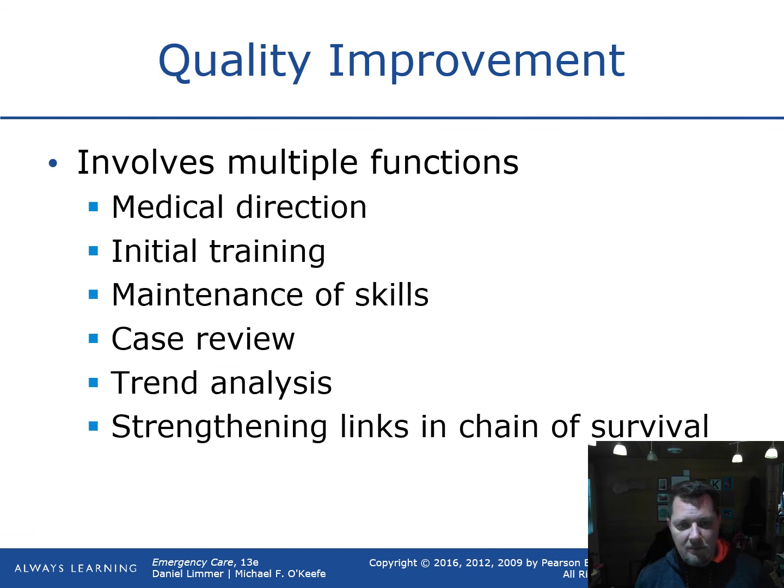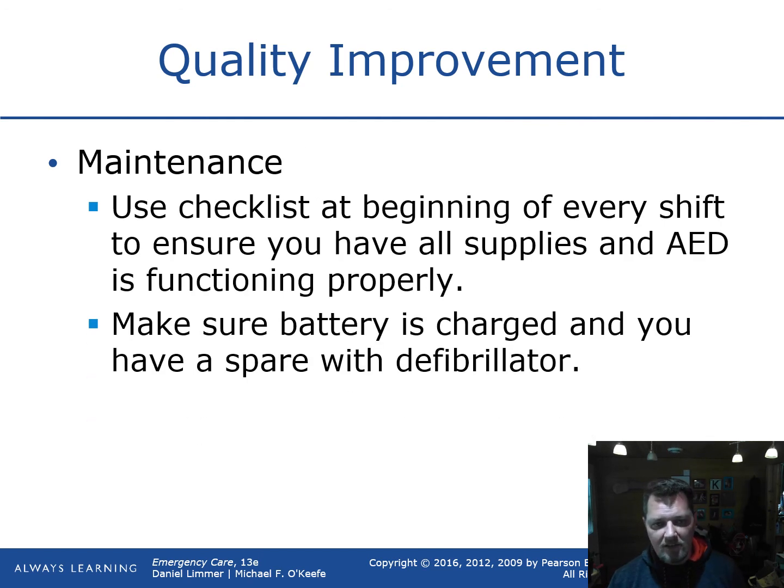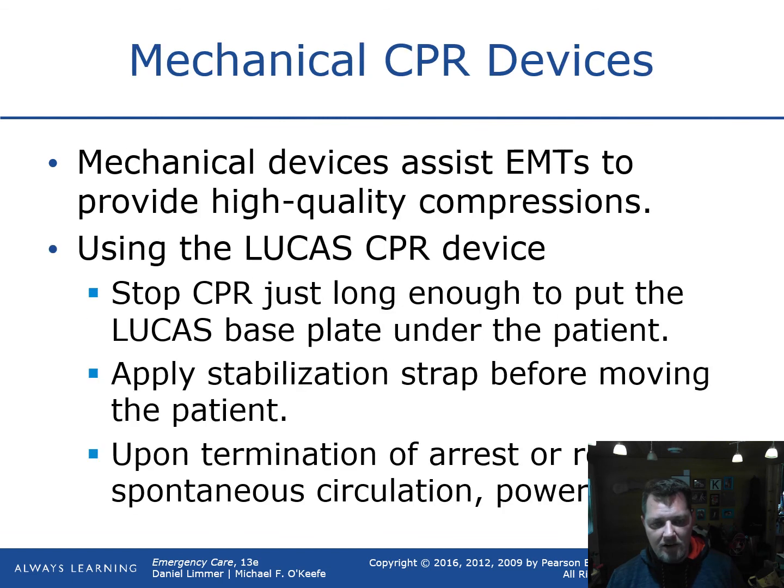So quality improvement involves multiple functions: medical direction, initial training, maintenance of skills, case review, trend analysis, and strengthening the links in the chain of survival. So maintenance, we're going to use a checklist at the beginning of every shift to ensure you have all supplies and the AED is functioning properly. Make sure the battery is charged and you have a spare with the defibrillator.